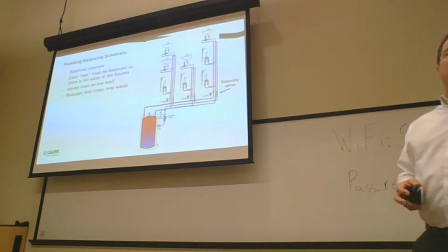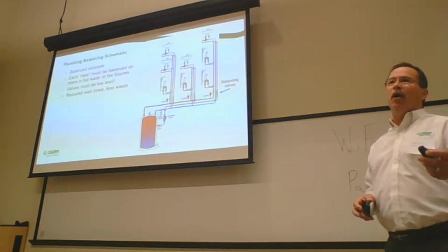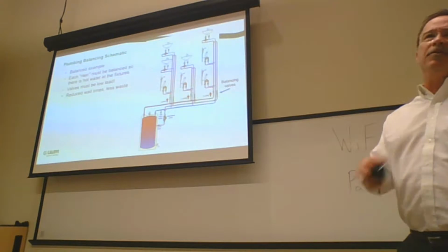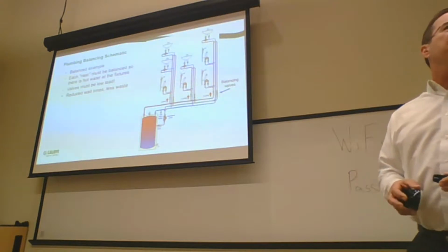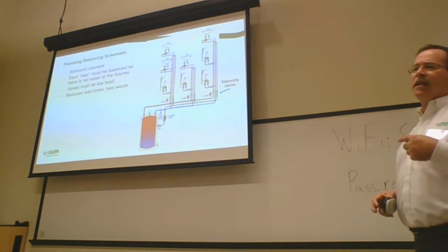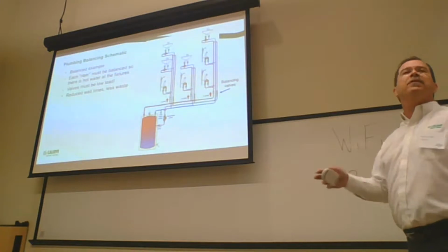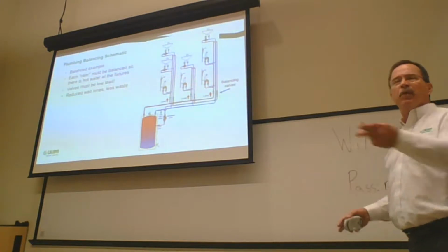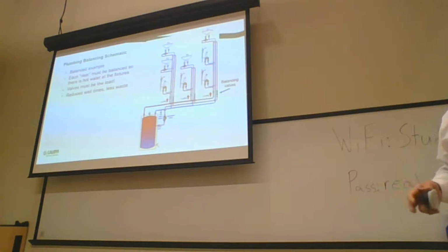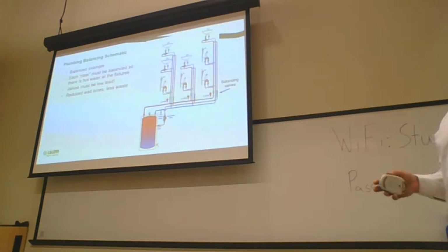And they can be 3/4 pipe, even 1/2 inch pipe, because you only need a few GPM. All you're really doing is getting enough hot water as close as you can to that fixture so that it's available for the user. You can think of these domestic recirc systems as a closed system. Okay, the whole system is open because you open a faucet and it brings in fresh water and this water is all oxygenated. But in terms of thinking about the pump and the balancing, you can think of it as a closed circuit, especially at night when nobody's drawing water. Technically, it is a closed circuit.